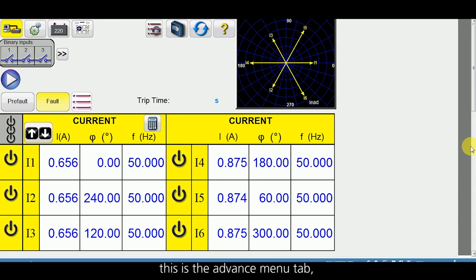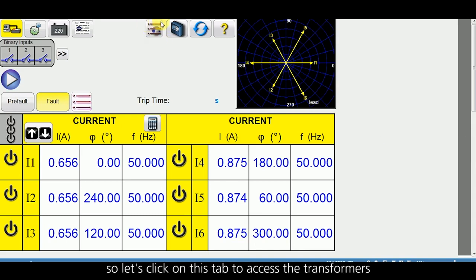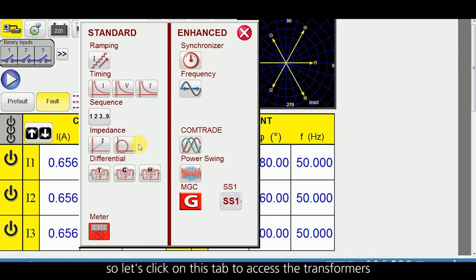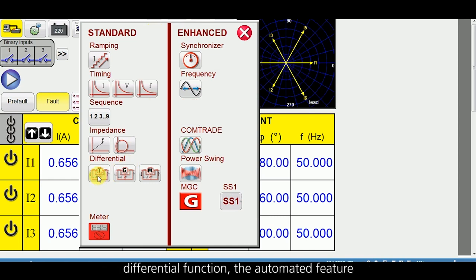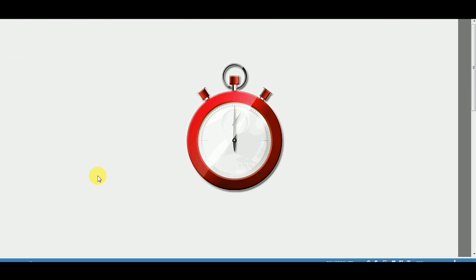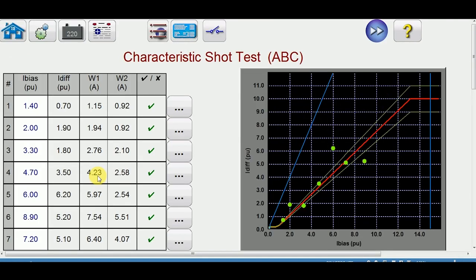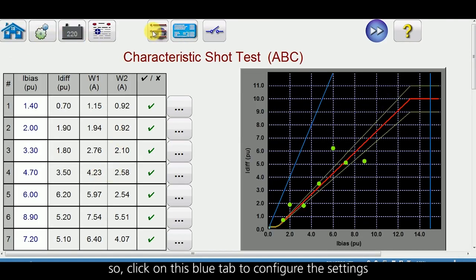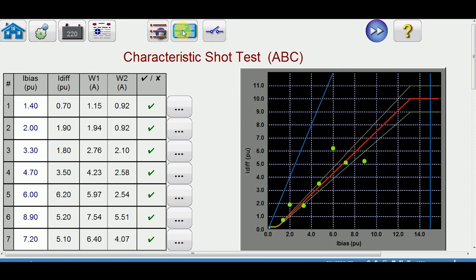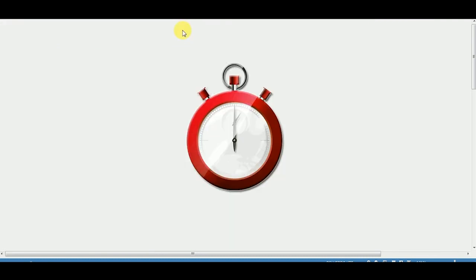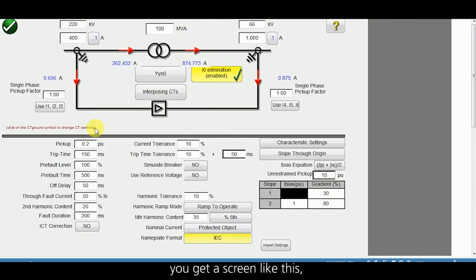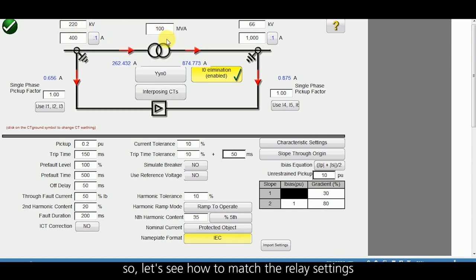This is the advanced menu tab. Click on this tab to access the transformer differential function — the automated feature. Click on this blue tab to configure the settings. Once you click on the blue tab you get a screen like this. Here we need to enter the values to match the relay settings. Let us see how to match the relay settings.